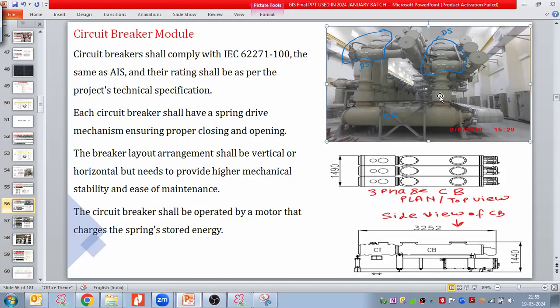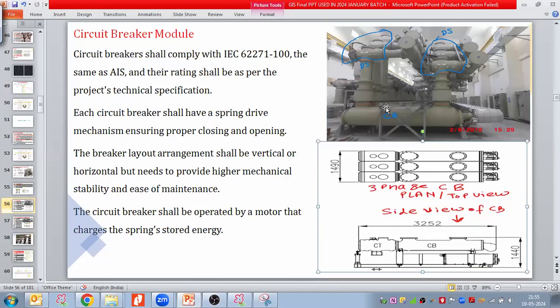So let us see how this breaker module looks. It is the site photo. Here we have the breaker, and this is the snapshot of the GIS drawing, showing how they indicate the breaker. This portion of the drawing represents the breaker, from here to here. This is your operating mechanism. This is the site view, and this is how it appears in the drawing. So this is the breaker module in the drawing, and this is how it looks at the site.